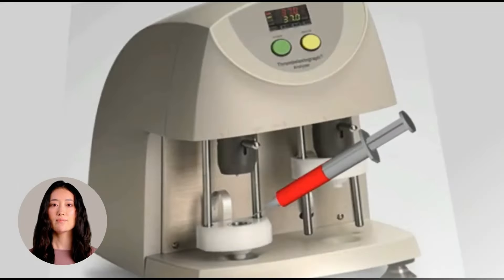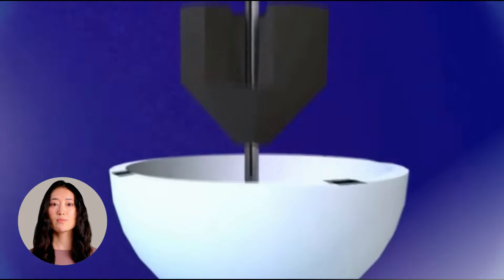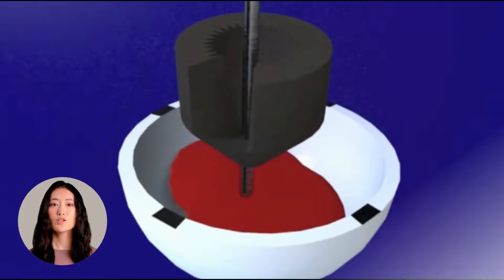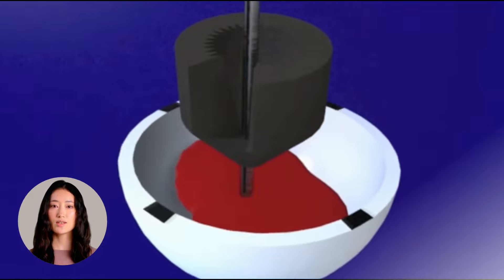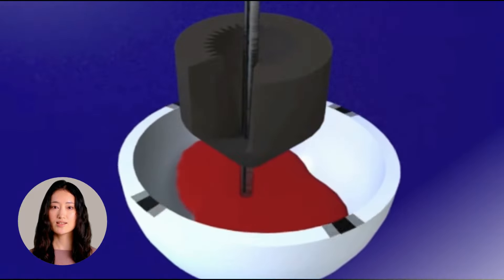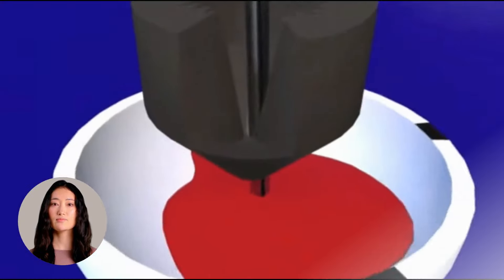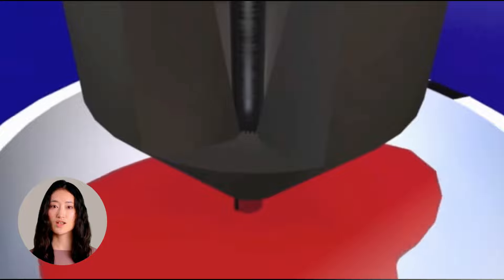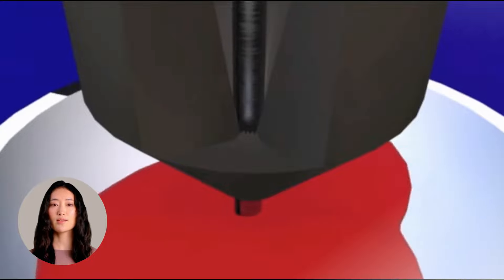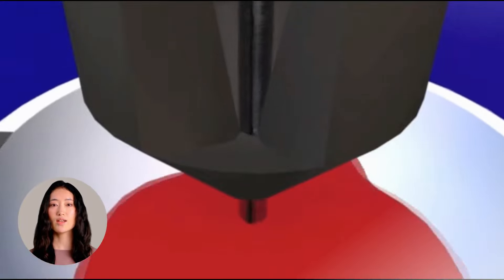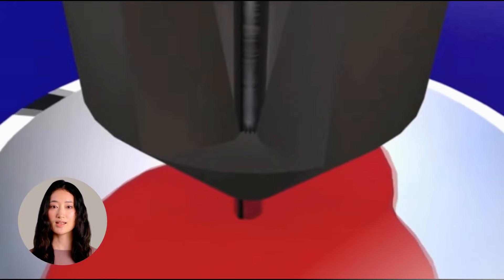The test is done by adding the citrated blood into the sample cup of the TEG machine. The cup oscillates around a submerged torsion pin which is connected to a computer. As coagulation occurs, the pin adheres to the clot and starts to move with it. The magnitude of the pin motion is directly related to the strength of the clot, and pin motion is displayed graphically by the computer.